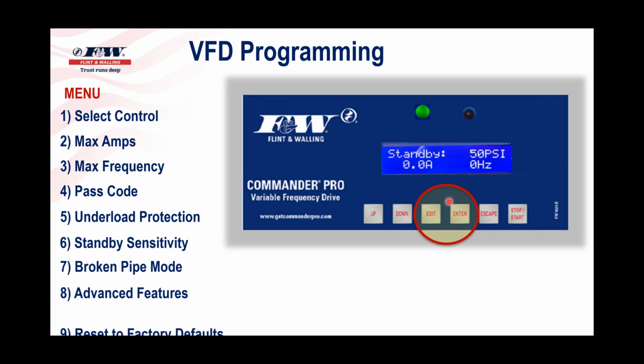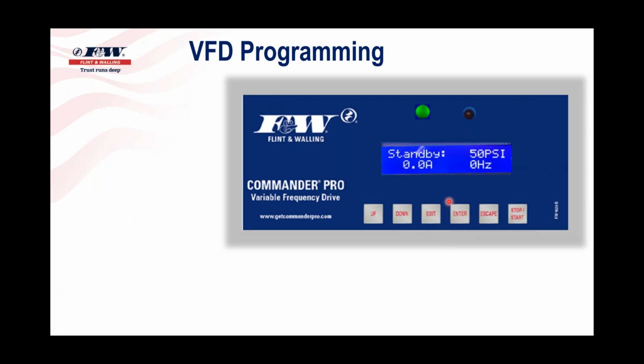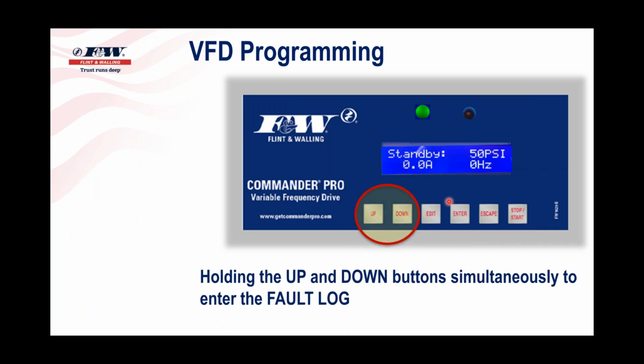Then there's advanced features. You get down to menu 9, and that takes you back to the factory default. So at a later date and another web conference topic, I'm going to go into some of the advanced programming and settings as we try to get more topics coming up. The other thing I'd tell you about is if you use the up and down buttons, you hold those simultaneously, just like you did the edit and enter buttons to get into the programming. If you walk up to our drive and you press the up and down buttons and you hold them down just for a few seconds, you're going to enter into our fault log.